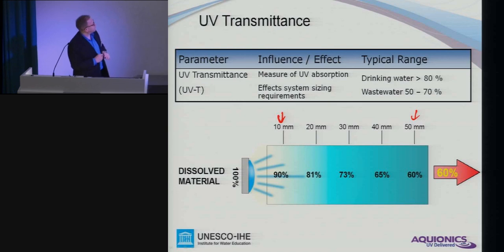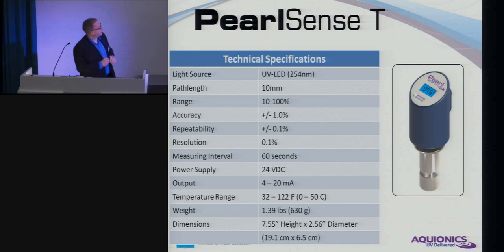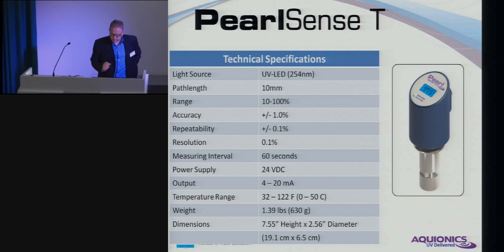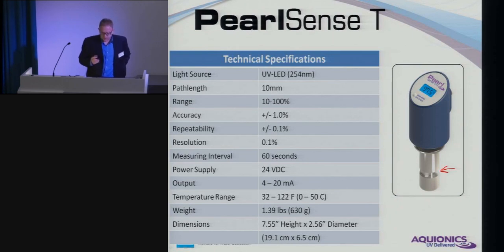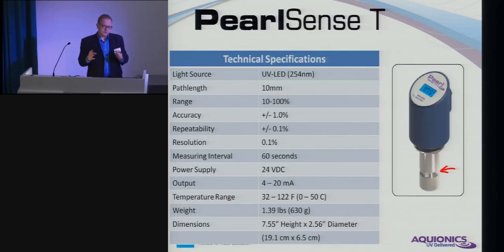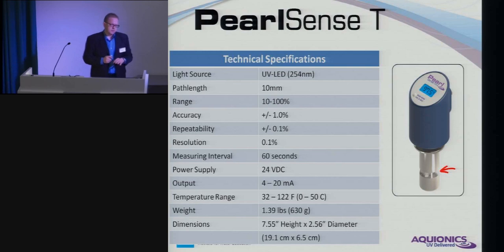The resulting product — and I also have one on display in the hallway — is the Pearl Sense T. It's using one LED. It's still expensive, but we only need one, so it's competitively priced. It measures UVT with a one-centimeter gap, measuring a path length of 10 millimeters. We can measure anything in the range of 10 to 100% UVT, which allows either designing or operating a system. Depending on the testing protocol, the system would be able to dim down or ramp up the lamp power, optimizing power consumption while ensuring enough UV is always applied for proper disinfection.